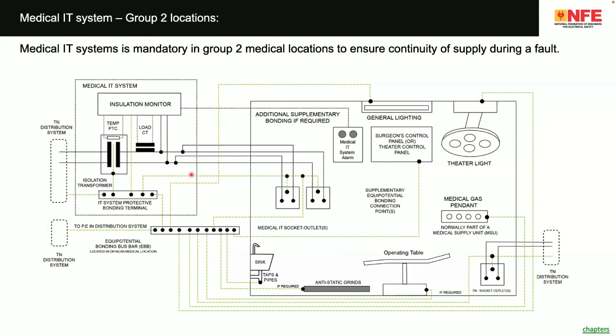Now, imagine in the pendant you have 16 plus 16, maybe about 20, 30 plug points. Once maybe 10 are already used, and if somebody puts a faulty equipment on a plug point, and if the circuit trips, then you are in danger. If you use a medical IT system, even if you put a faulty device into the socket, the system doesn't trip. It will give you an alarm. So once you get an alarm, you can either disconnect the equipment, or you don't need to worry if you don't have an equipment. You can continue the operation. You can finish it. So this is very much essential. Also, this isolation ensures that some of the equipment, the EMI, electromagnetic requirements are met.